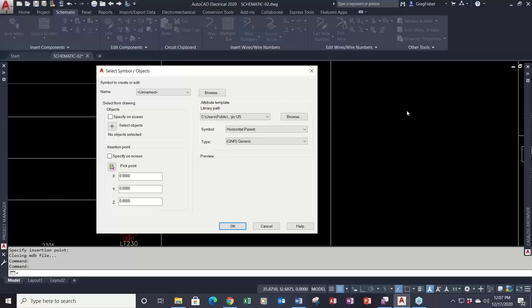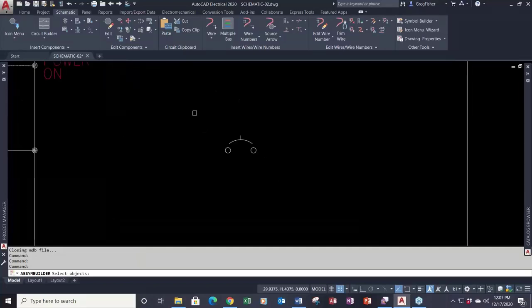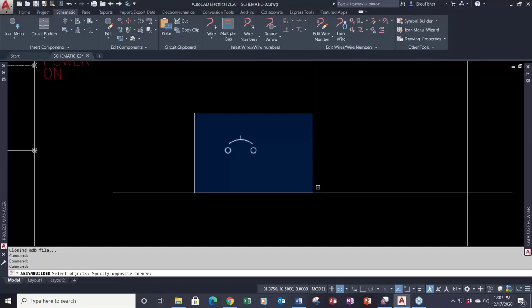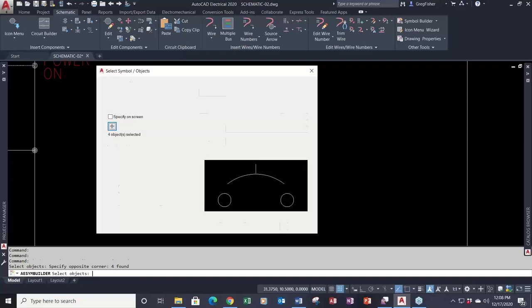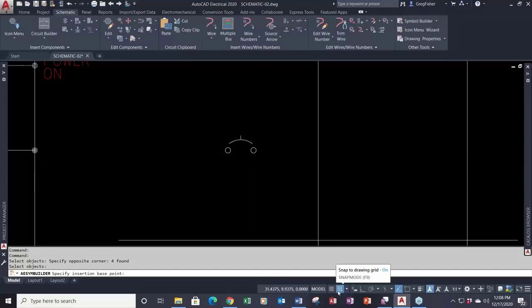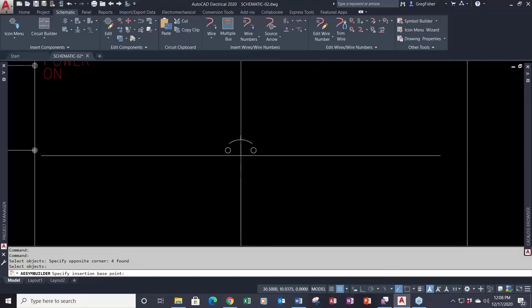First thing we do is select your objects, just like you normally would when creating a block. I'll wrap a window around the graphics of this breaker. For the graphics in your symbol, you're going to use AutoCAD lines, arcs, circles, polylines — whatever you want to build in. It's very important that all your graphics are on layer zero when you create the symbol. When you insert it, AutoCAD Electrical automatically puts it on the correct layer.